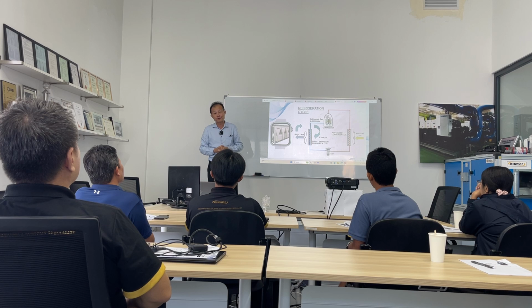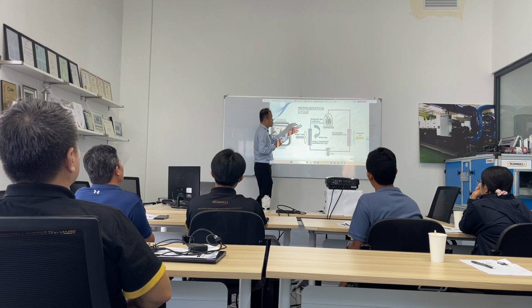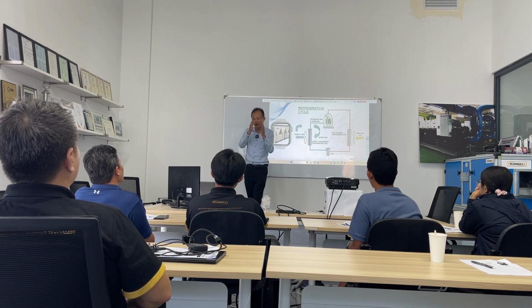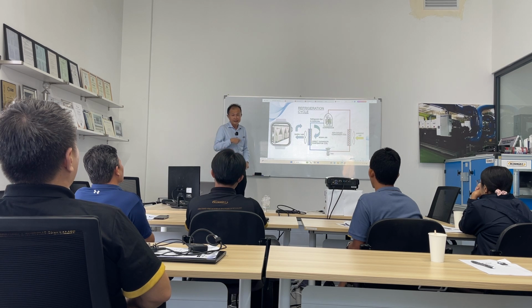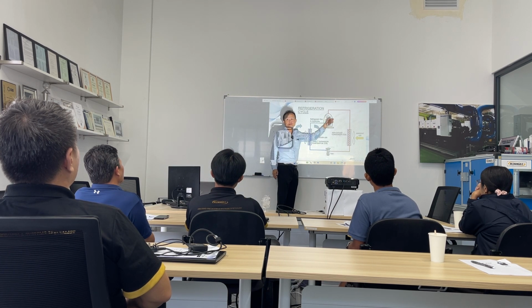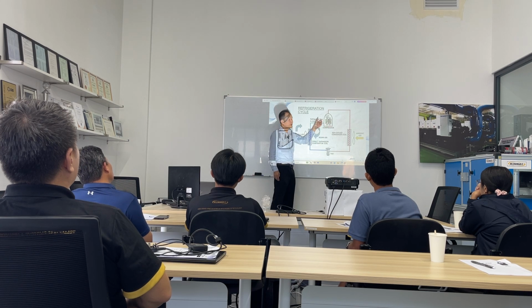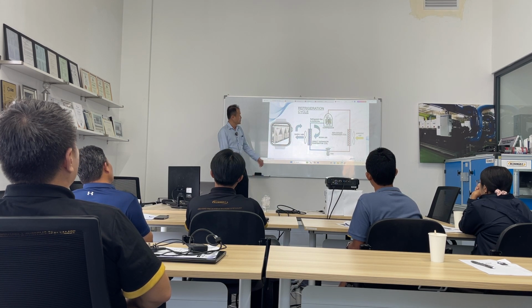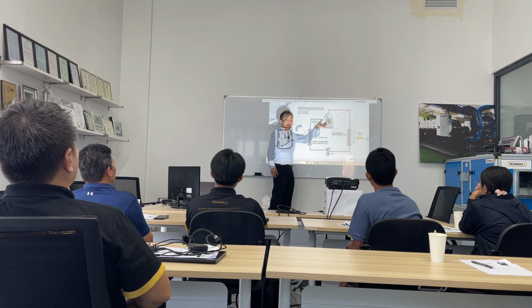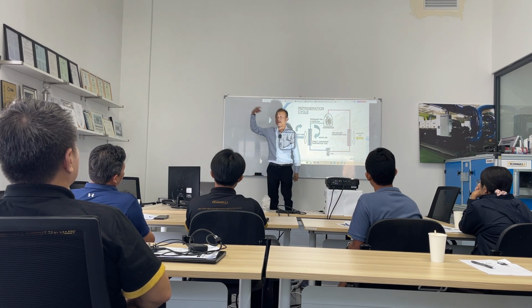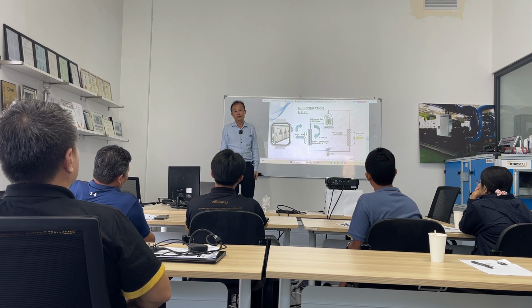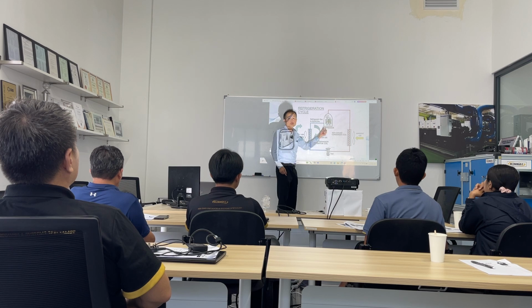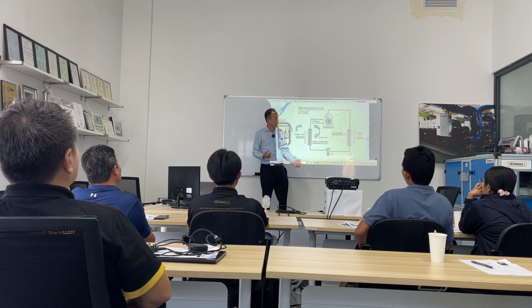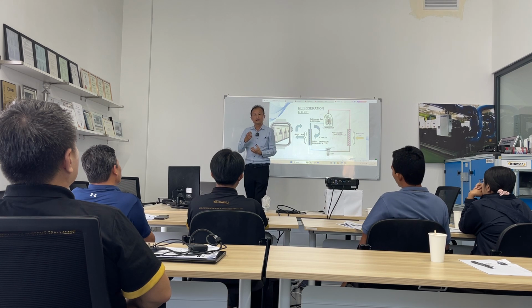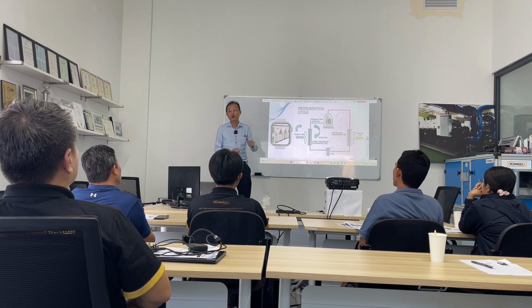This is actually against the basic principle of thermodynamics. When you need to transfer heat from low temperature to high temperature, you need to do some work. That work is carried out by the compressor, which raises the pressure and temperature in the condenser to higher than the outdoor temperature. When you do this work, you need to consume a lot of power. The work carried out by the compressor needs a lot of power. That power comes from TNB.